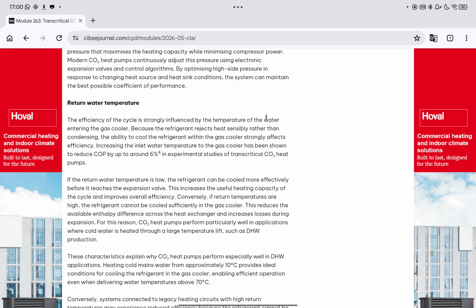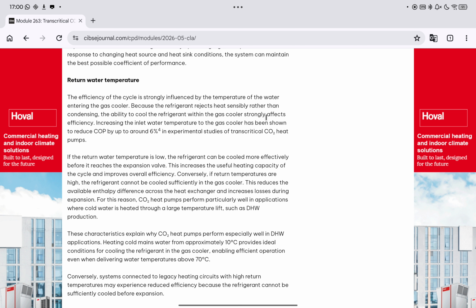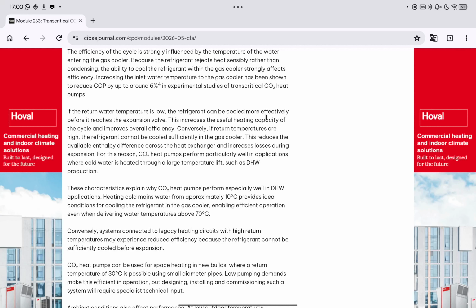If the return water temperature is low, the refrigerant can be cooled more effectively before it reaches the expansion valve. This increases the useful heating capacity of the cycle and improves overall efficiency. Conversely, if return temperatures are high, the refrigerant cannot be cooled sufficiently in the gas cooler. This reduces the available enthalpy difference across the heat exchanger and increases losses during expansion. For this reason, CO₂ heat pumps perform particularly well in applications where cold water is heated through a large temperature lift, such as DHW production. These characteristics explain why CO₂ heat pumps perform especially well in DHW applications.